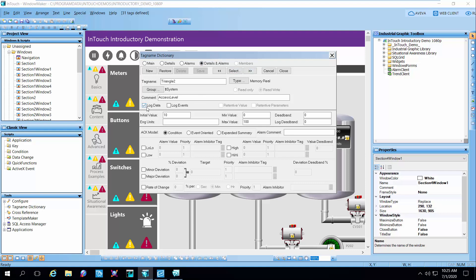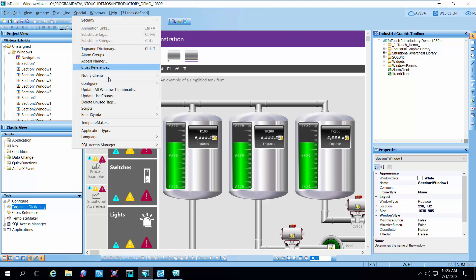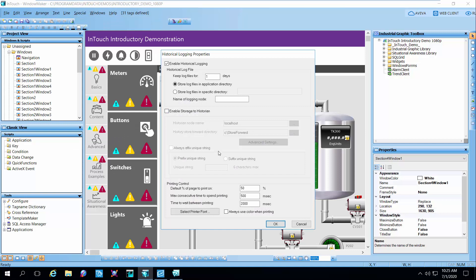This checkbox here that says log data — that's not new, that's been around for a long time, but we need to have that checked to be able to push the data to the Wonderware historian. The other setting we need to do is configure the historical logging under configure historical logging. What's new here is the ability to enable storage to the historian — that's a new feature with 2020. We have to give it the name of our historian, the host name. In this case it's just localhost because everything is running on one box.